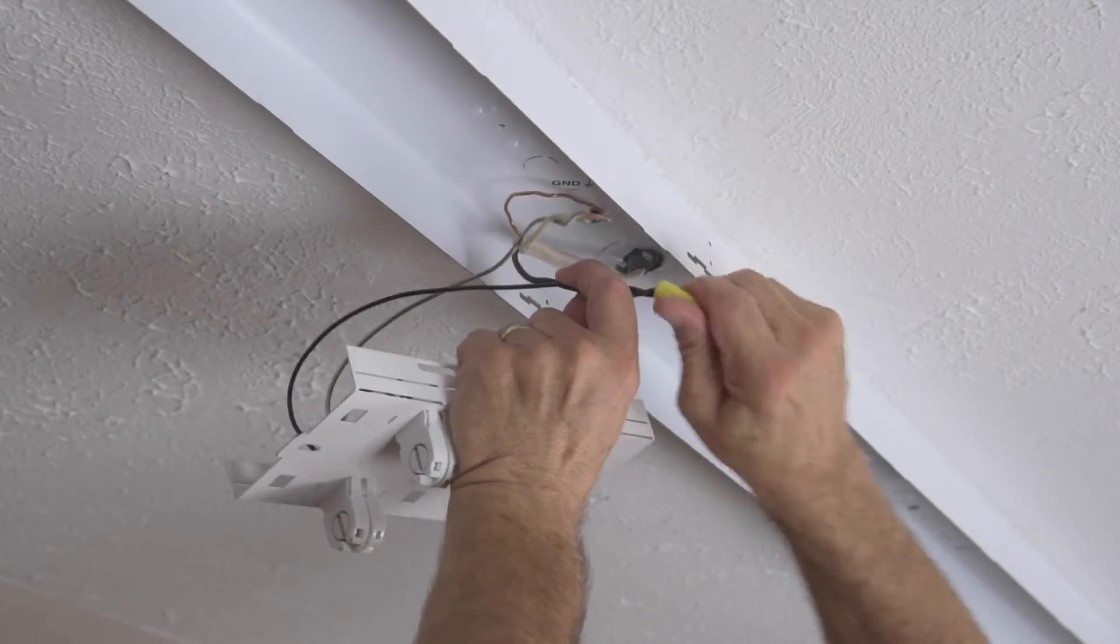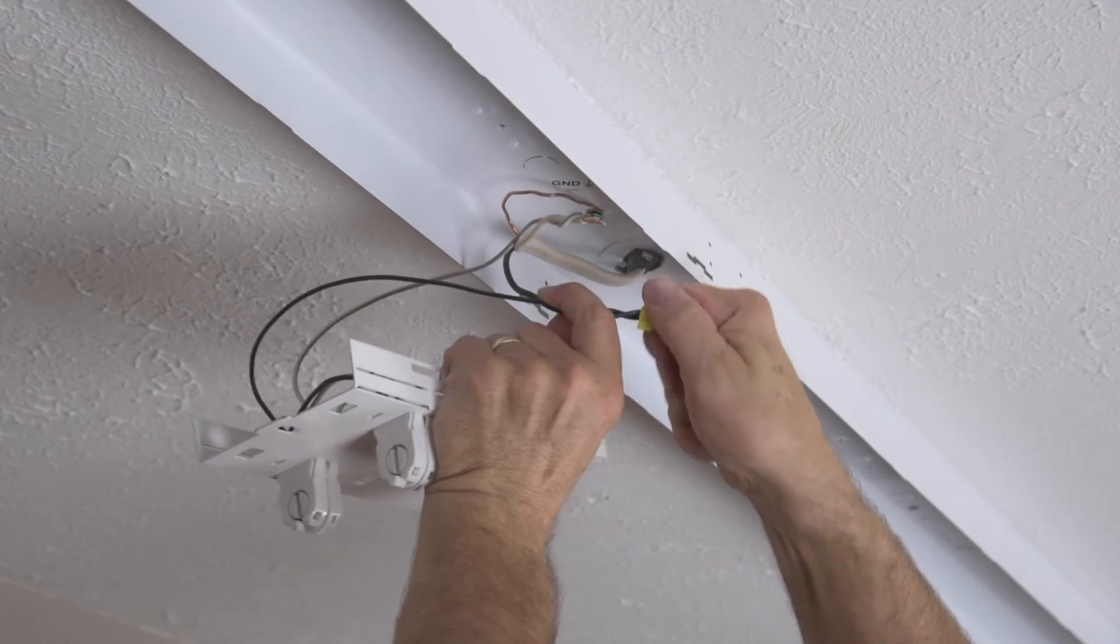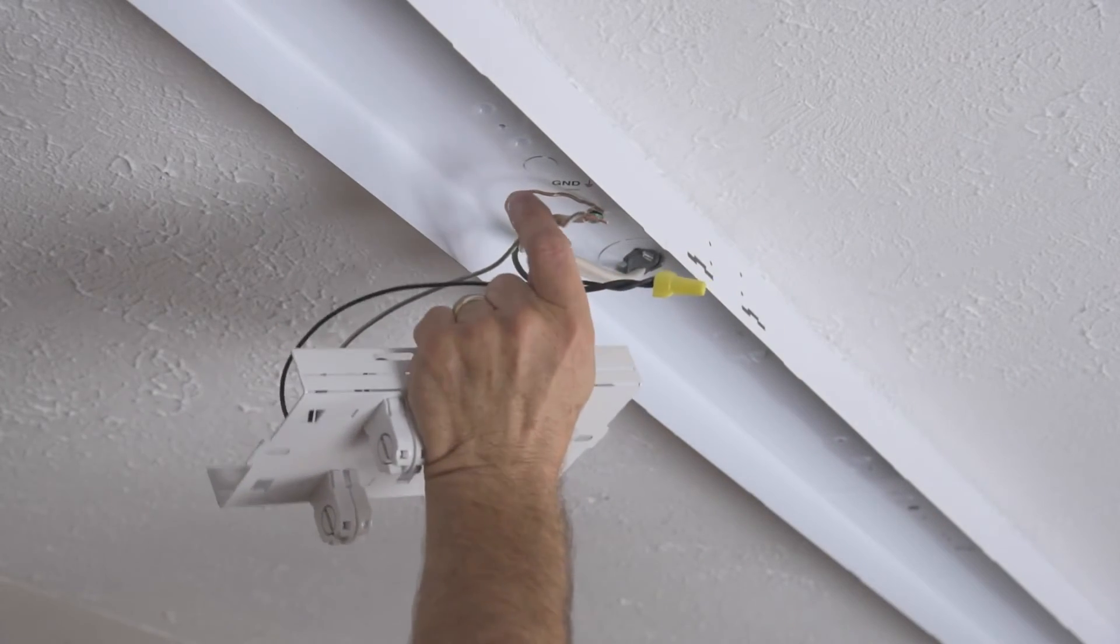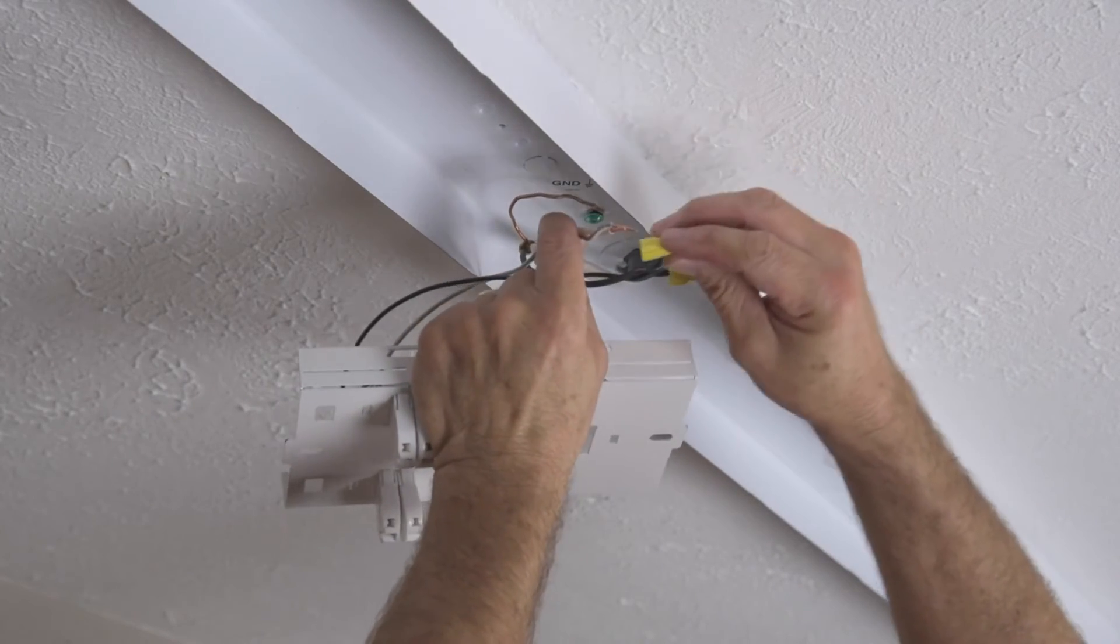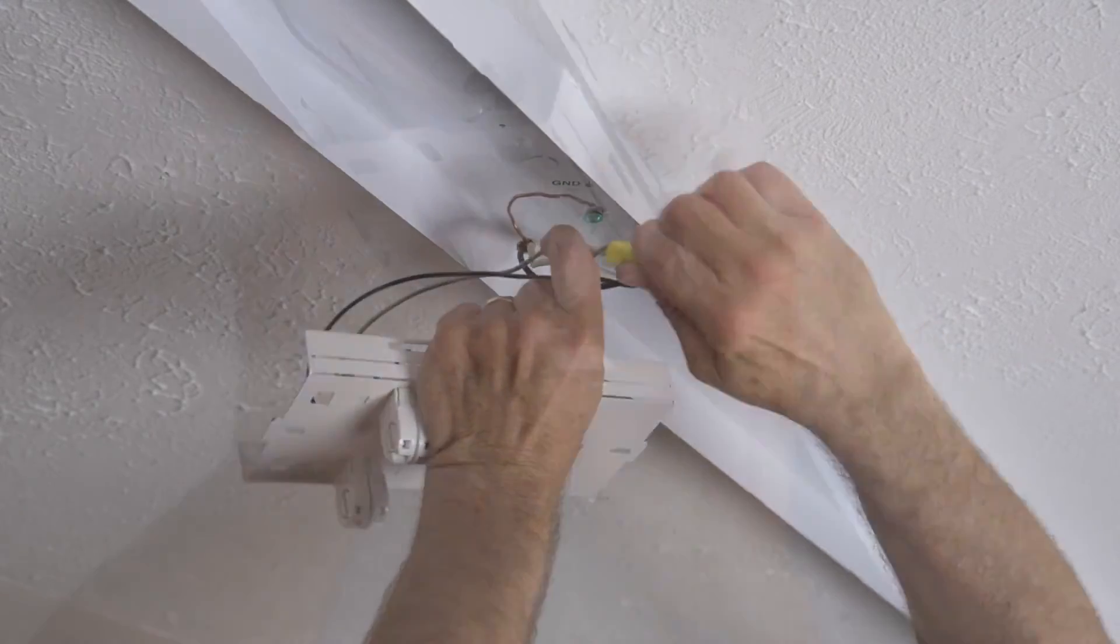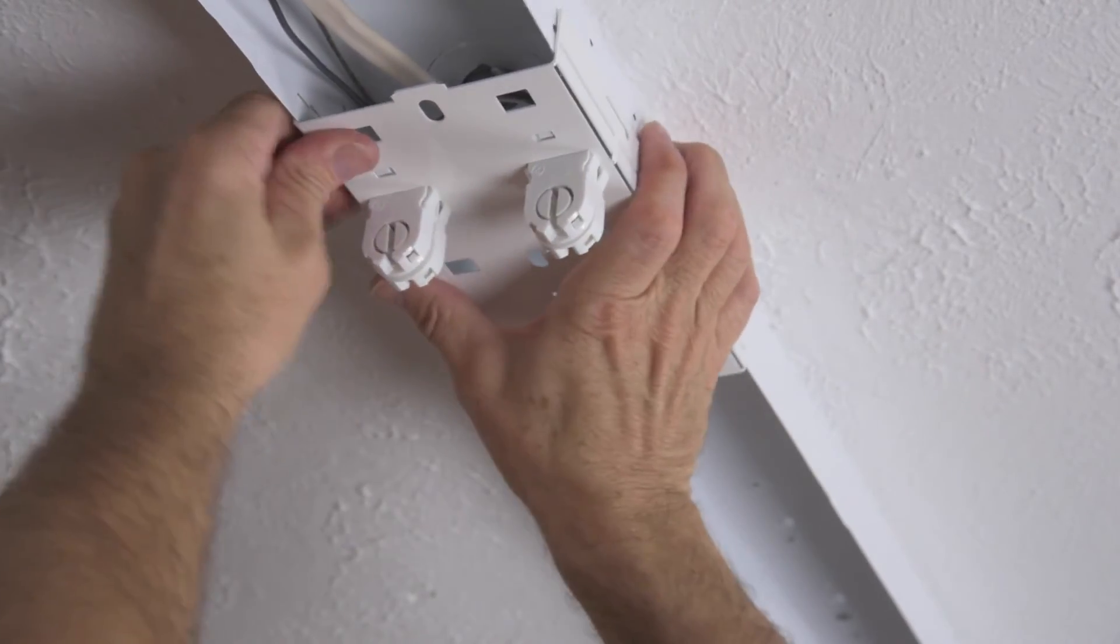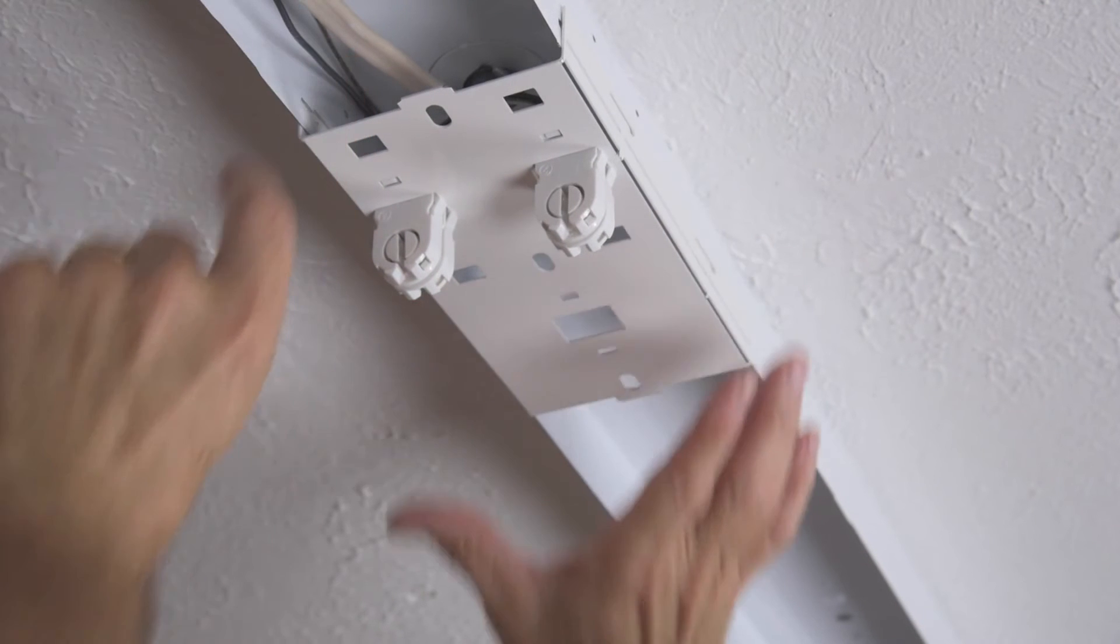Now connect the lead wires to the wires from the outlet box using wire nuts. Black to black, white to white. Then tuck the wires up into the fixture. Pressure fit the center mount to the fixture.